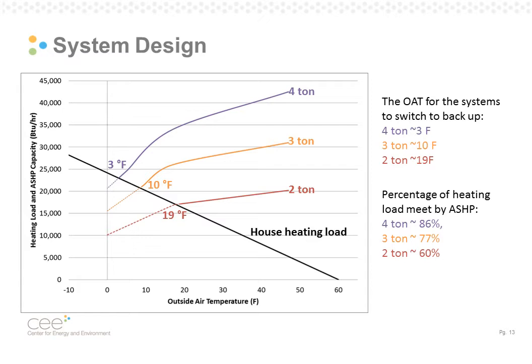So the higher tonnage means the unit can meet a higher percent of the heat load of the home. If you look on the right side of the slide, the 2-ton unit could meet 60% of the heat load of the home, while the 3-ton is 77%, and the 4-ton can meet about 86% of this home's heating load. So for the 3 units installed, the systems were sized to meet the heating load of the home down to 10 degrees Fahrenheit.